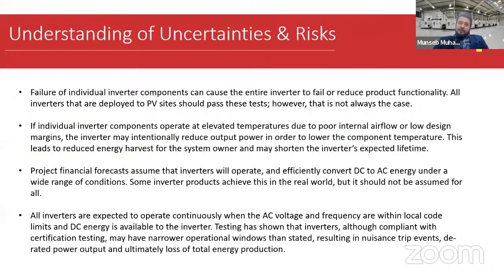So we need to understand the uncertainties and the risk involved here. The failure of inverter components can cause the entire inverter to fail or reduce power functionality. All inverters that are developed on the PV side should pass this test, but in practice this is not the case. So if an individual inverter component operates at an elevated temperature due to poor internal airflow or low design margins, the inverter may intentionally reduce the output power in order to lower the component temperature.